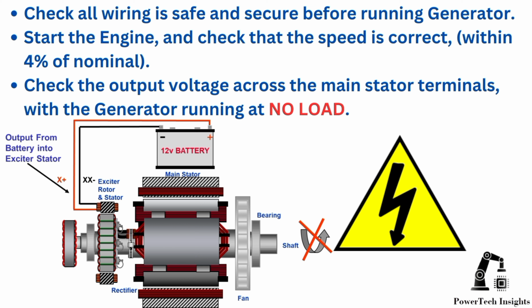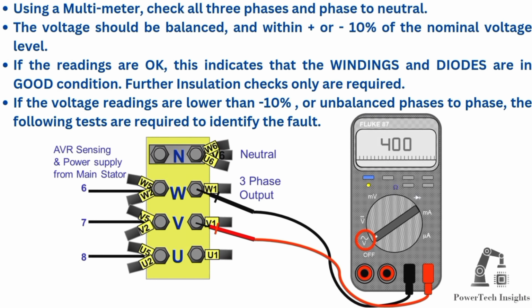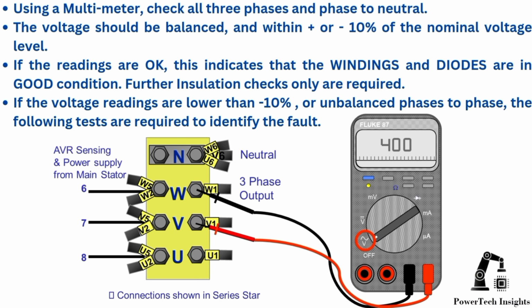Remove lockout-tagout, LOTO. Start the engine and check that the speed is correct, within 4% of nominal. Check the output voltage across the main stator terminals with the generator running at no load. Using a multimeter, check all 3 phases and phase to neutral. The voltage should be balanced and within plus or minus 10% of the nominal voltage level. If the readings are okay, this indicates that the windings and diodes are in good condition. Further insulation checks only are required.